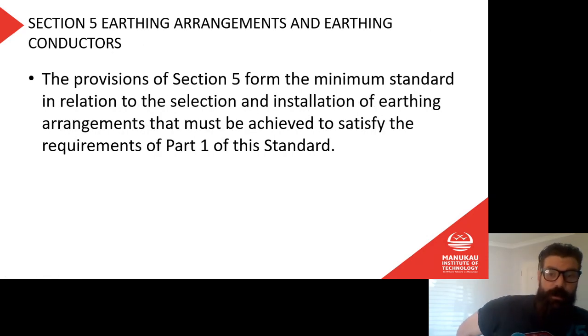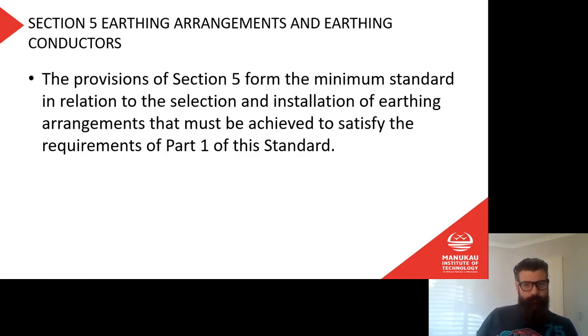Section 5 is about earthing arrangements and earthing conductors. So it provides the minimum standard for the selection and installation of earthing arrangements. So earthing is our main earth stake outside the building. It'll cover the cable that will run from that earth stake into the switchboard, how we connect all our earths in the switchboard, how the earth going out to our sub-circuits, into our sockets and lights and stuff needs to work. We haven't covered yet all of the stuff around earthing, like what is earthing, what is it for, how does it work, but nevertheless, if we need any information about earthing, this is the section that we go to.